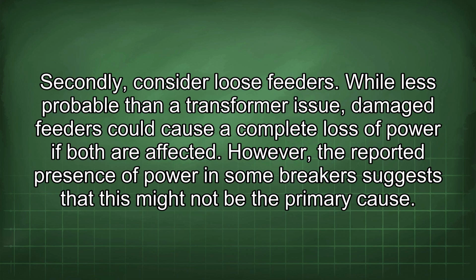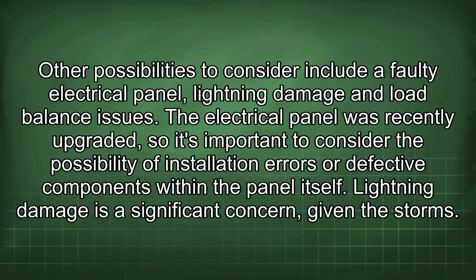Secondly, consider loose feeders. While less probable than a transformer issue, damaged feeders could cause a complete loss of power if both are affected. However, the reported presence of power in some breakers suggests that this might not be the primary cause. Other possibilities to consider include a faulty electrical panel, lightning damage, and load balance issues.